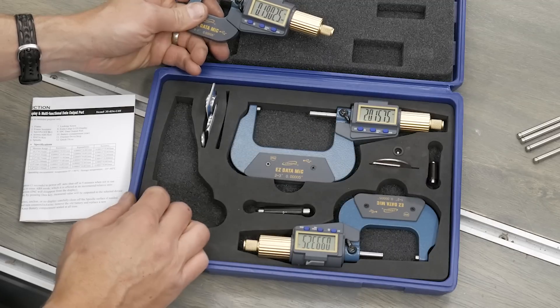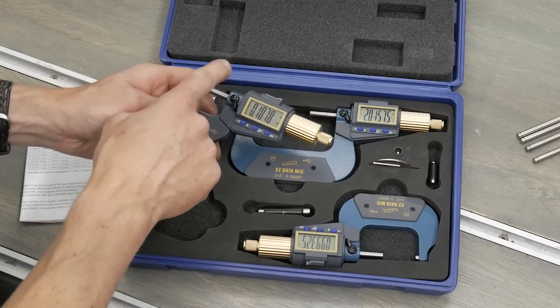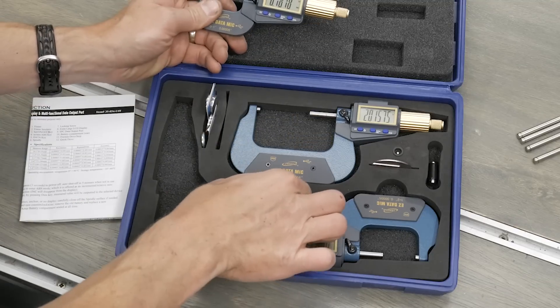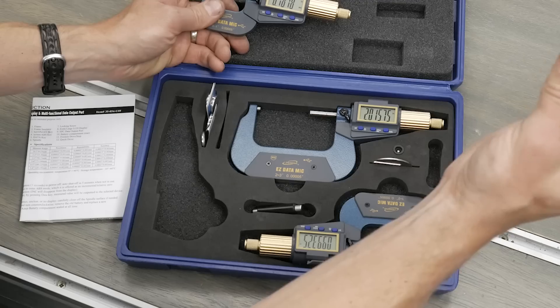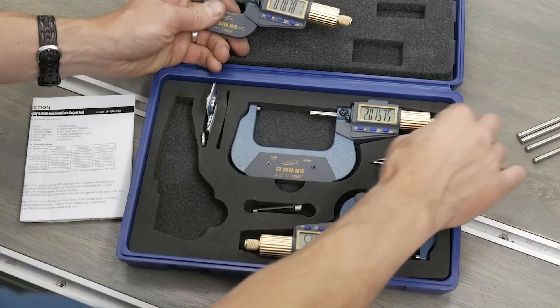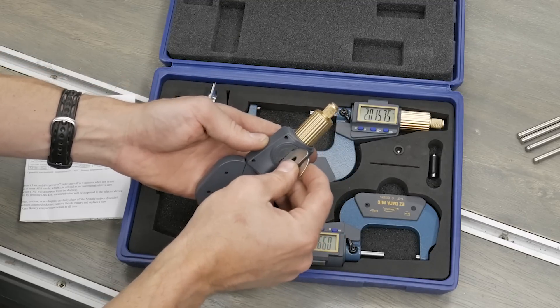It has the tools that you need to calibrate. None required for the 0-1 because you do that with the anvil closed. It's got the 2-inch for the 2-3 and it's got the 1-inch for the 1-2. It comes with a special tool that helps to open and close the battery door on the back.